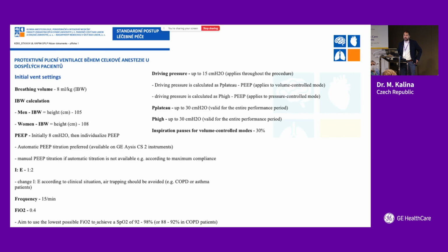And we wanted to test how our physicians applied our protocol, and we know from our educational sessions that if you have anesthesia machines from different companies, if you set PEEP 4, for example, in some companies it will be lower than actually 4 if you measure it on a separate ventilation simulator. So then we choose the higher recommended value, 8, because then we know that all of our anesthesia machines will be in real range between 6 and 8.